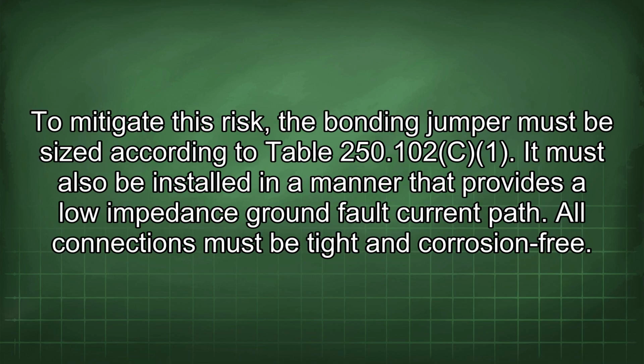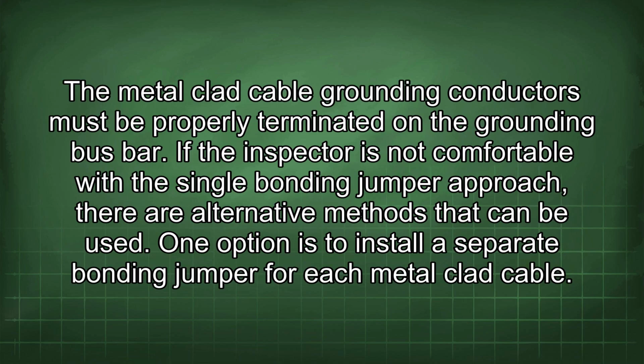To mitigate this risk, the bonding jumper must be sized according to Table 250.102(C)(1). It must also be installed in a manner that provides a low impedance ground fault current path. All connections must be tight and corrosion-free. The metal-clad cable grounding conductors must be properly terminated on the grounding bus bar. If the inspector is not comfortable with the single bonding jumper approach, there are alternative methods that can be used.